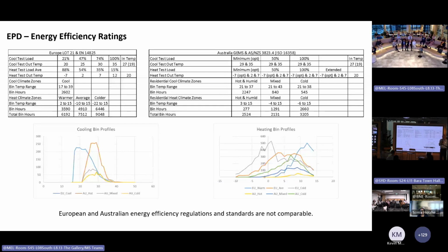So talking about energy efficiency ratings, I'm quite involved with energy efficiency ratings. I'm making a small comparison between the European rating system and the Australian rating system. So when you do a calculation to work out the efficiency, in Europe it's SEER, or Seasonal Energy Efficiency Ratio, and SCOP, Seasonal Coefficient of Performance. We use a different measure, which is called TCSPF, Total Cooling Seasonal Performance Factor, and HSPF, Heating Seasonal Performance Factor. They're worked out to different standards. For instance, in Europe, it's a European standard. We have a European regulation, Lot 21. In Australia, we have our own regulation, the GEMS Act. And we use the international standard, the ISO standard. We have different testing points.